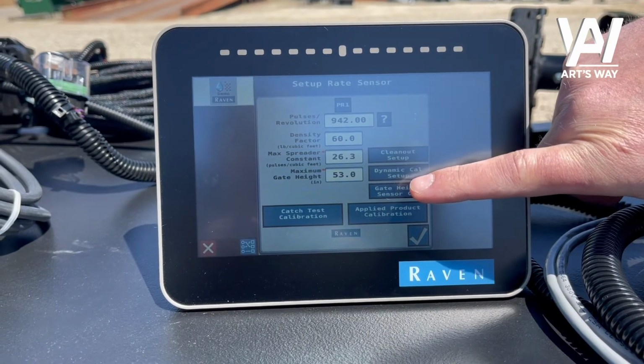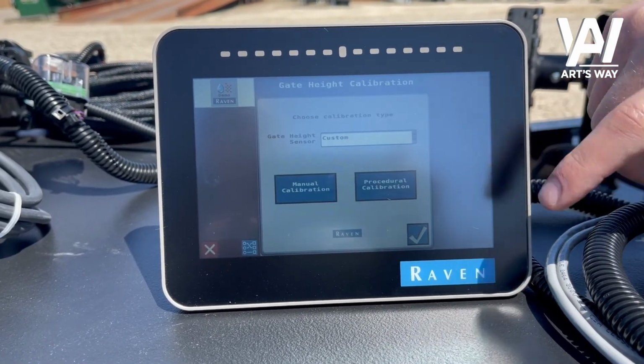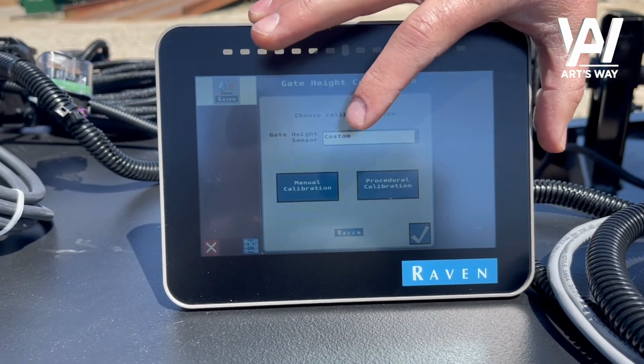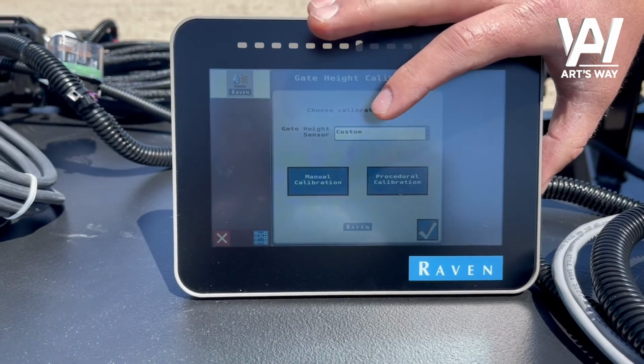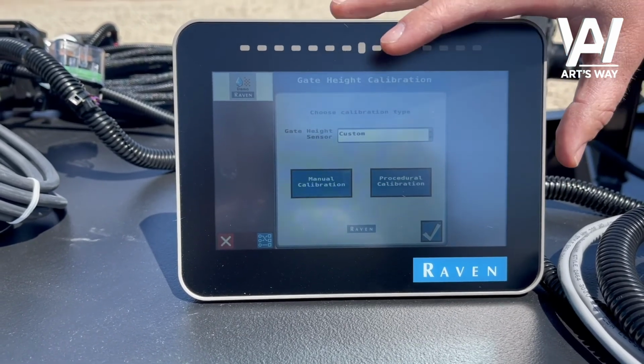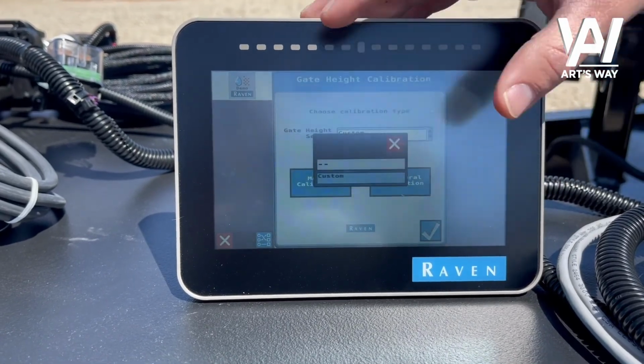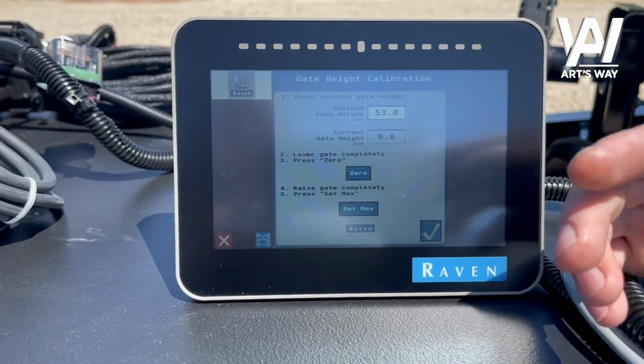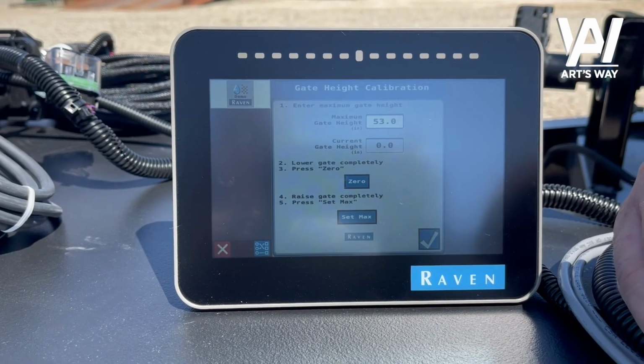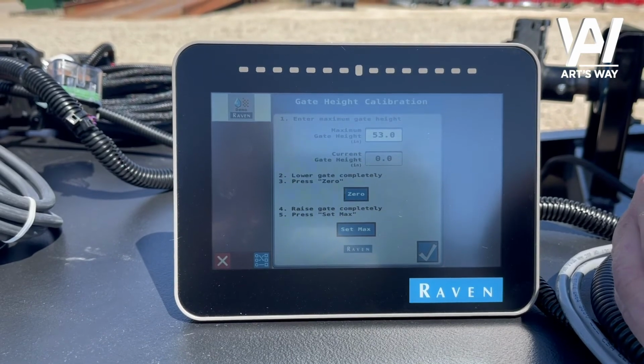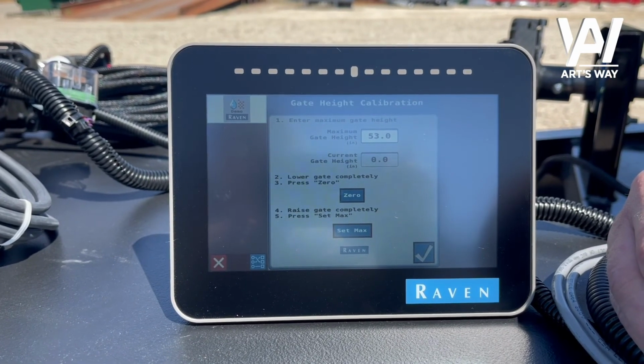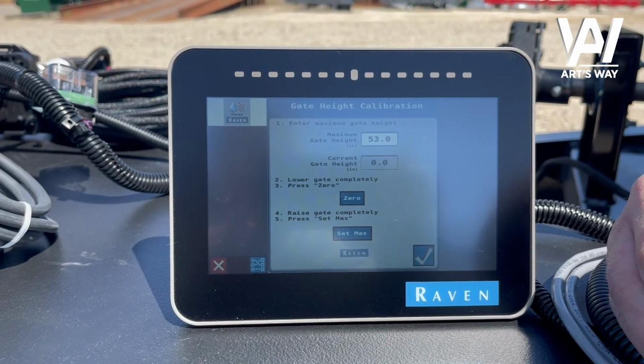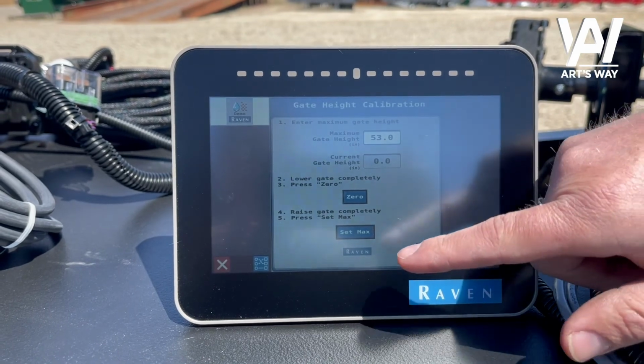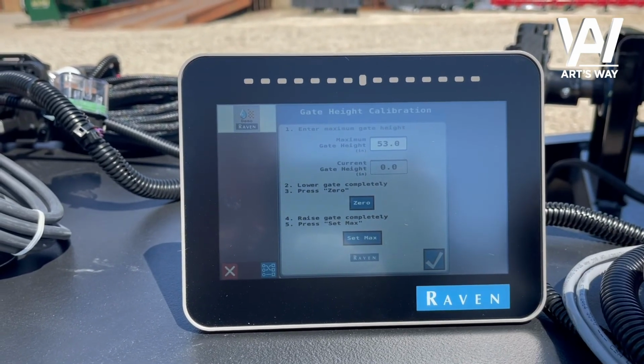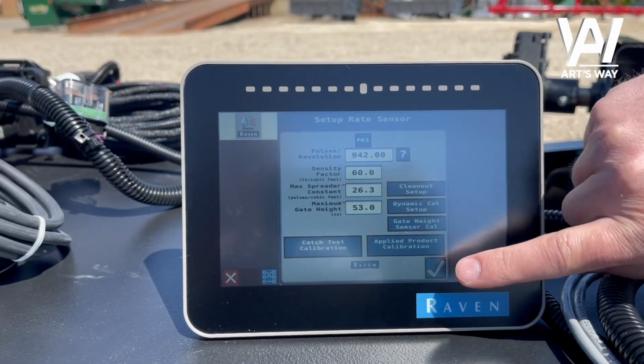One other thing you'll have to do for the gate height sensor is an initial calibration. Again, this should come from the factory already done, but if for some reason things get reset and you have to go back through it, go into your gate height cal. In the drop down, you'll choose custom, and then we'll go to our procedural calibration. It's pretty straightforward how we step you through this. Essentially, you'll have your max gate height setting in there. You'll lower the gate all the way and zero it out, and then you'll simply raise the gate and set your max. From there, the gate calibration is complete. You can check out of there and return to the home screen.